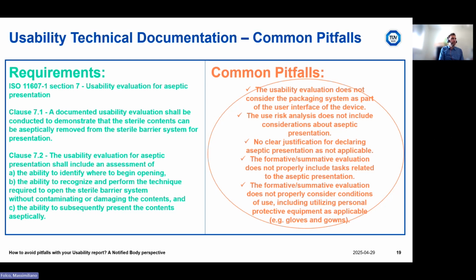This standard requires a usability evaluation specific for the aseptic presentation of the sterile contents when removed from the sterile barrier system. The usability evaluation shall include an assessment of the ability to identify where to begin opening, the ability to recognize and perform the technique required to open the sterile barrier system without contaminating or damaging the contents, and the ability to subsequently present the contents aseptically. These are three typical tasks that are required to be included in a usability evaluation, if possible, in the overall usability evaluation of the product, in order to have a complete usability evaluation, starting from the unpacking of the device until its disposal, so following the entire life cycle of the device.